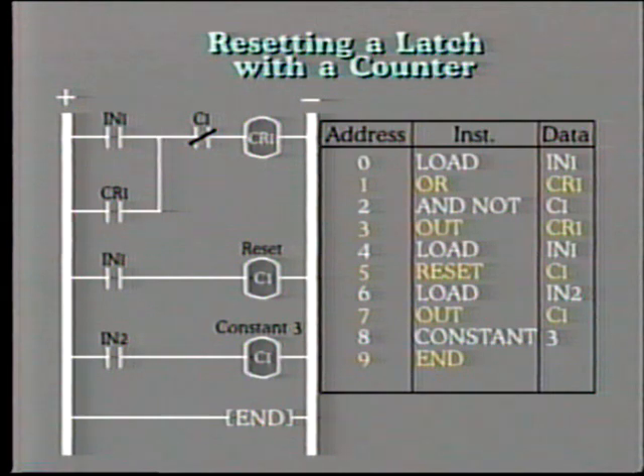Of course, this auxiliary relay is not a relay in the true sense of the word. It is merely a function which is part of the software program. In many programmers, this enables us to include latching and unlatching arrangements by simply entering the appropriate function. This logic circuit shows us how the latch could be reset using a counter. When the push button IN1 is pressed, it resets the counter as well as energizing the control relay CR1. Each time that contact IN2 is closed, it is registered by the counter. After 3 operations, the counter output is energized, and this in turn opens contacts CR1, so breaking the seal and unlatching the primary circuit.